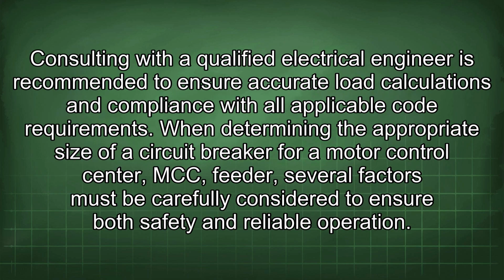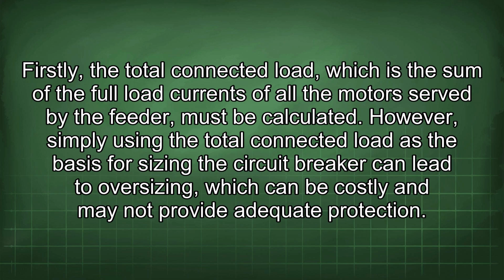Consulting with a qualified electrical engineer is recommended to ensure accurate load calculations and compliance with all applicable code requirements. When determining the appropriate size of a circuit breaker for a motor control center (MCC) feeder, several factors must be carefully considered to ensure both safety and reliable operation. Firstly, the total connected load, which is the sum of the full load currents of all the motors served by the feeder, must be calculated.